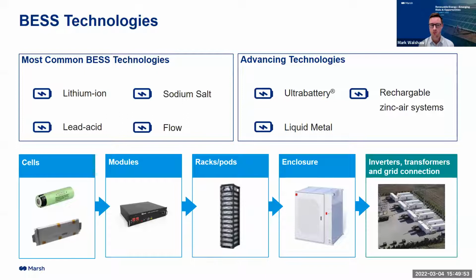At cell and module levels, one of the real safety factors we see is that there's battery management systems in place. These are monitoring the thermal management and also the control to prevent battery abuse and failure, and these are very important. The battery management systems are often housed external to the battery enclosure to prevent any heat transfer, and often link into fire protection systems as well to enable a prompt emergency response if ever required.